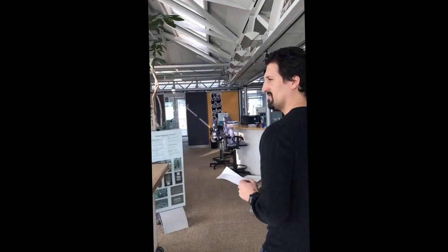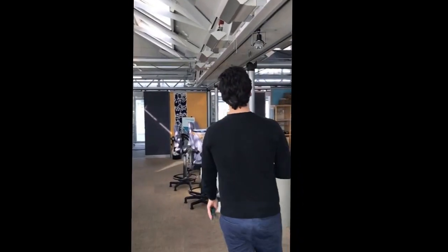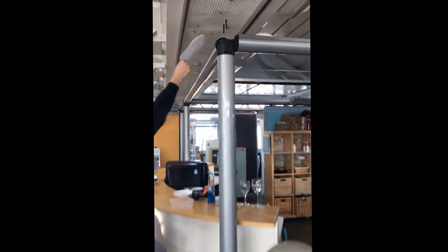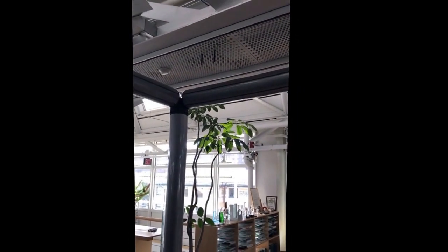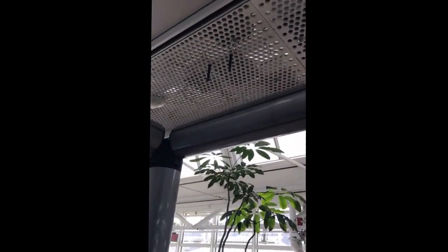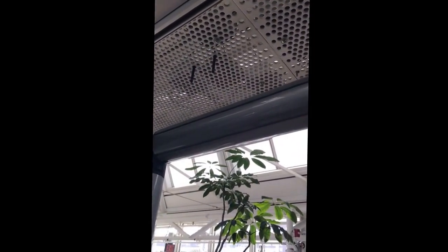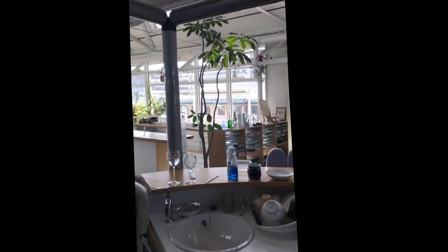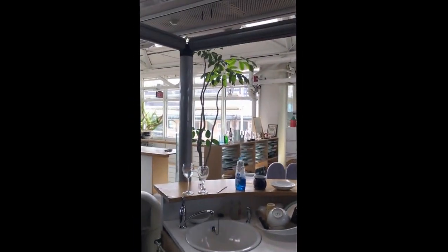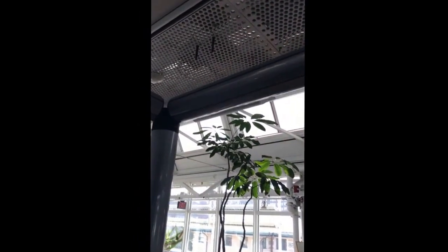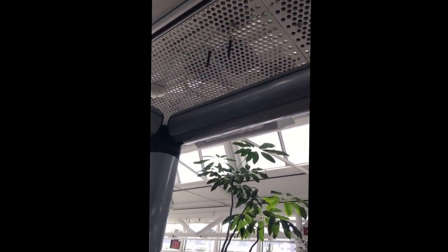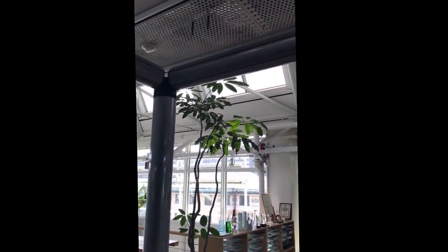It's wireless EnOcean technology, so it goes the other way, which is this one. The 2 antennas. All the sensors at the operable doors and windows come here, and it comes back to here. We only see these 2 antennas, but the actual server device is downstairs, on top of the coffee room, just above the sink. You see this one device translates the EnOcean signal into a BACnet signal. That's how we query it.